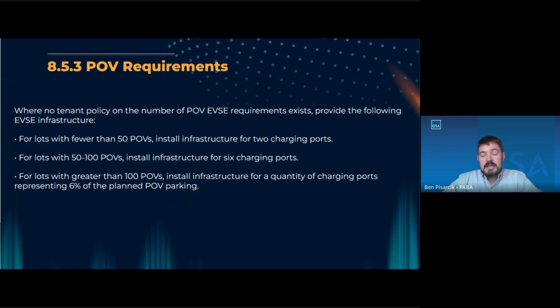Where no tenant policy exists, POV EVSE requirements provide the following infrastructure. When we say infrastructure here, we're talking about empty conduit. We want to install that empty conduit when the facility is being constructed, parking lots are being poured, parking buildings are being built, so that we have that pathway in the future. If we are funded to provide chargers for POVs, we can do that in the least intrusive way, as opposed to trenching concrete or asphalt. If the tenant doesn't have a policy, then P100 says for lots with fewer than 50 POVs, install infrastructure, conduits again, for two charging ports. For lots with 50 to 100, it would be six charging ports, and for greater than 100, 6% of the planned POV parking.